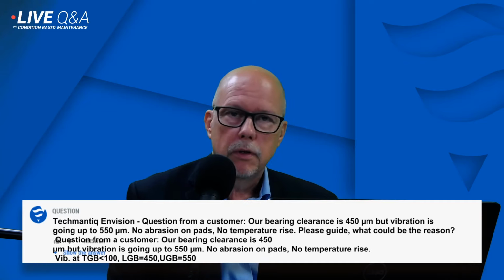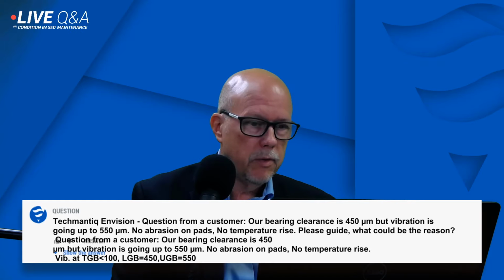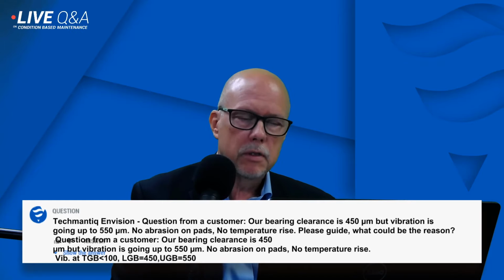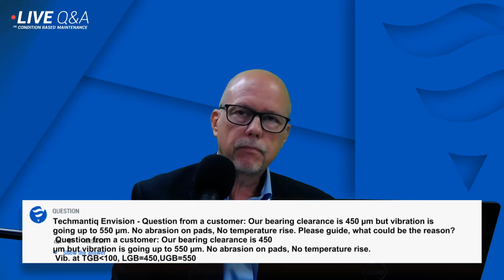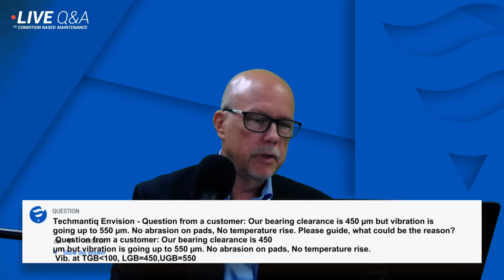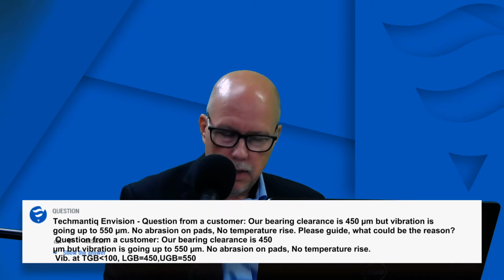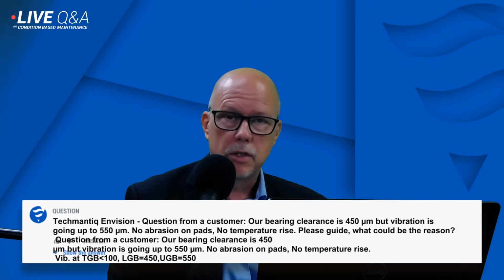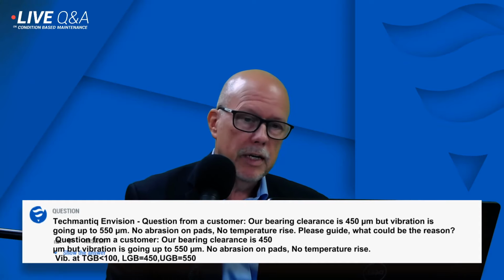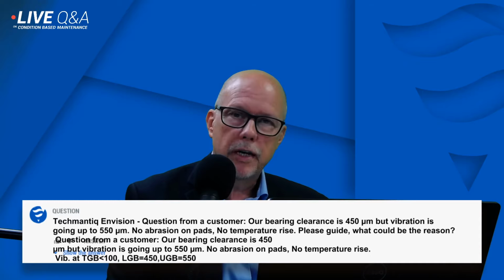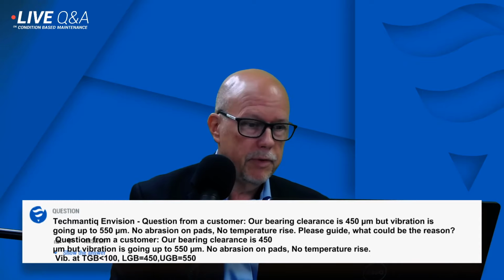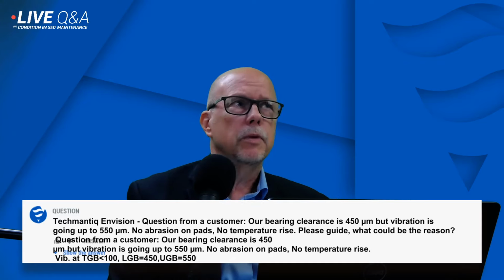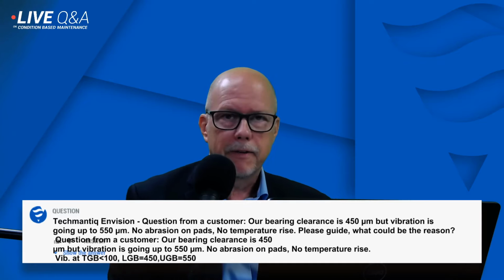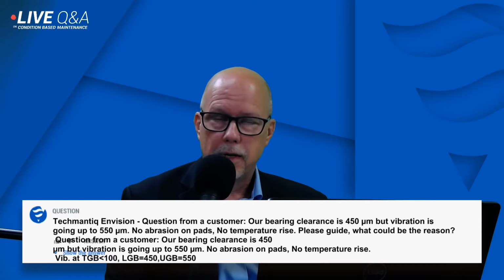Of course, I assume these readings are taken with shaft displacement probes, not accelerometers. When you have higher results at the shaft, higher than the actual bearing clearance, there's a few possibilities that come to mind. First and foremost, when you mention that the clearance is 450, is that the specified clearance, or is it actually what was measured? Because obviously during operation, if you have excessive vibration, that clearance will actually increase. So the first thing to check is to make sure that the clearance is still 450 microns peak to peak. In some cases also, when people use inductive probes, the calibration is incorrect, and you will measure more or less vibration than is actually the case.